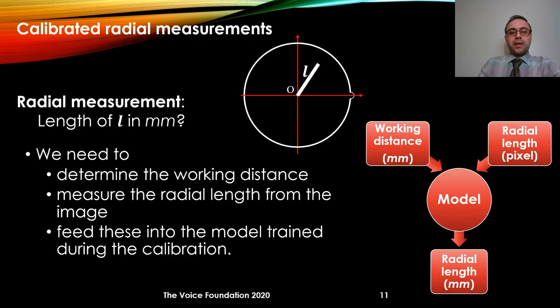During calibration, we created a model that takes working distance and radius of a circle in pixels and predicts the millimeter length of that radius. We can use that model for making measurements of any object that has one end at the center of the field. We find the working distance using the laser-based vertical measurement method, then measure the length L in pixels from the image, and feed these two inputs into the calibrated model, which then estimates the length L in millimeters.